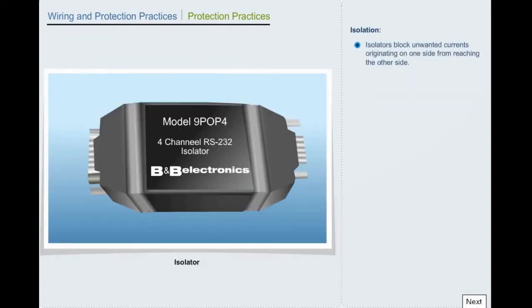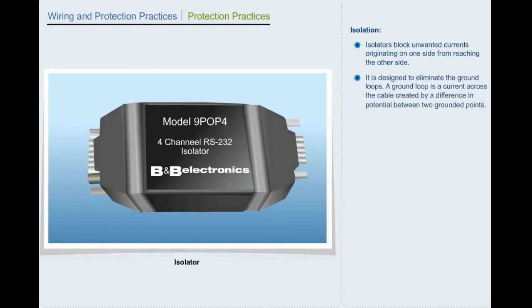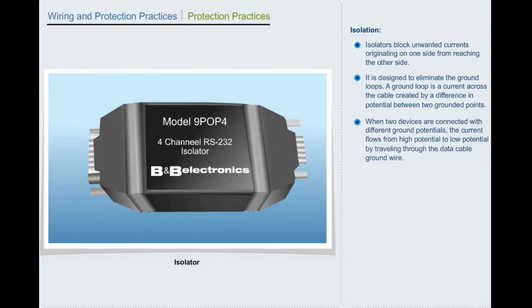Isolation. Isolators block unwanted currents originating on one side from reaching the other side. It is designed to eliminate the ground loops. A ground loop is a current across the cable created by a difference in potential between two grounded points. When two devices are connected with different ground potentials, the current flows from high potential to low potential by traveling through data cable ground wire. If the voltage difference is large, one of the RS-232 port can be damaged. Small potential difference can cause data transmission errors.